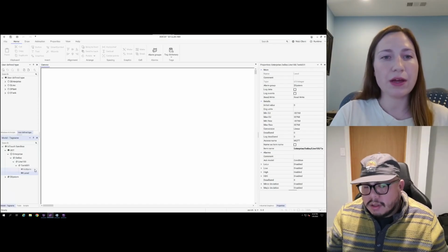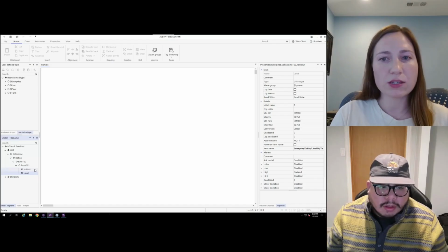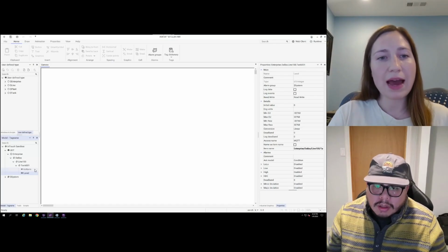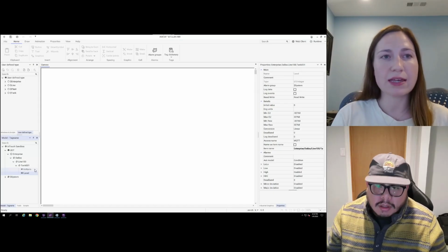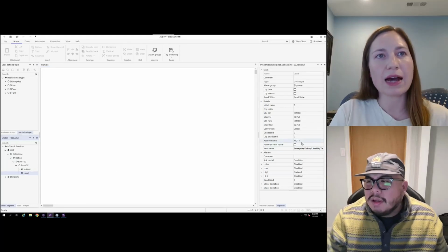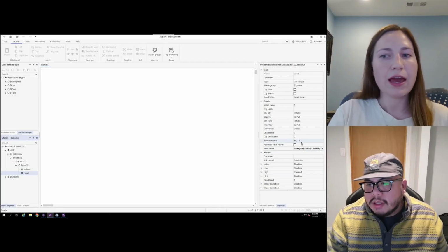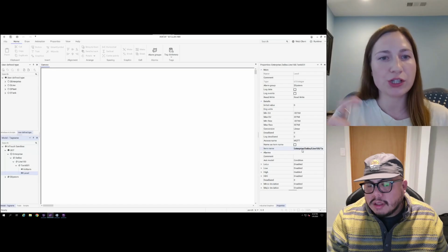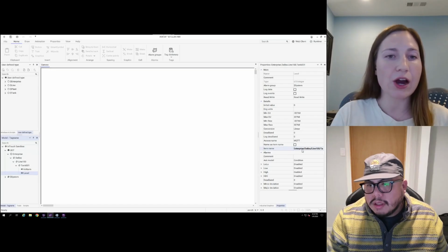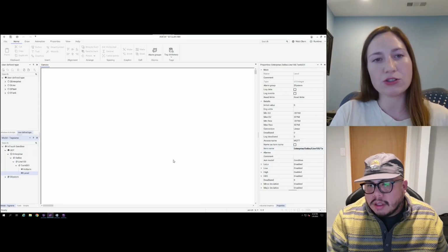And then what I can do is publish my model to my MQTT broker as the topic hierarchy. That way, within my MQTT broker, I'm following those same ISA 95 standards. For example, for my level tag here, I have my access name pointing to that MQTT access name I created earlier. And then I have my item name, which creates that topic hierarchy to align with the ISA 95 standards, which matches my UDT structure here.